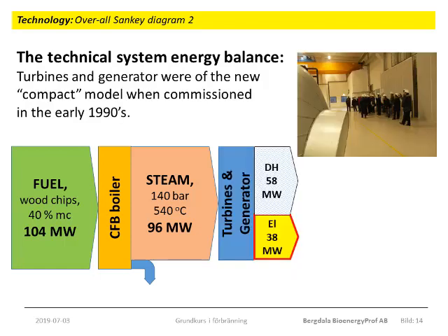The turbines, a high pressure turbine and a low pressure turbine, and the generator only have 38 megawatt generating capacity, which was enough when the plant was commissioned. The losses in the district heat exchangers are negligible, so the district heating will then amount to about 58 megawatt.